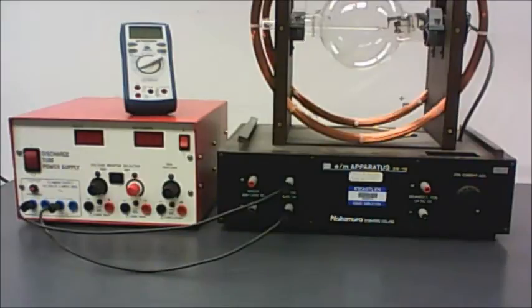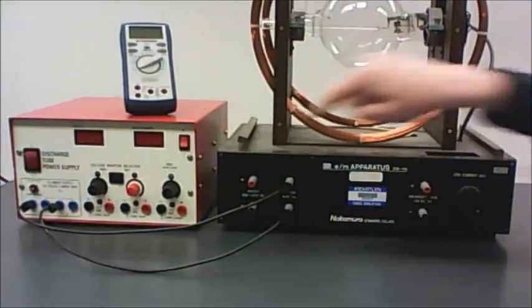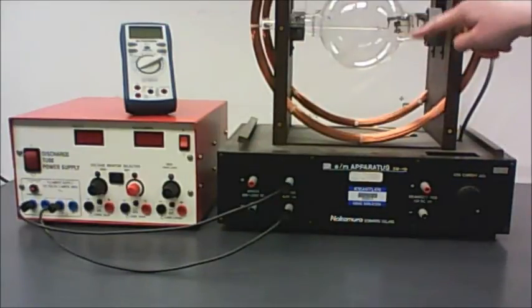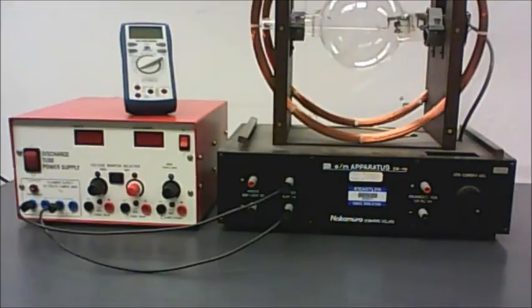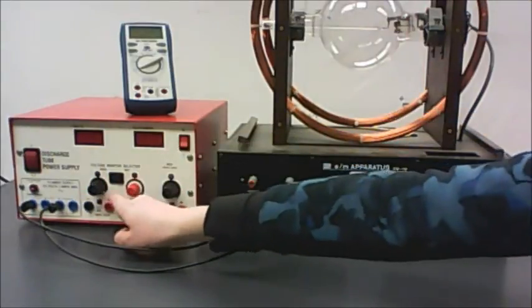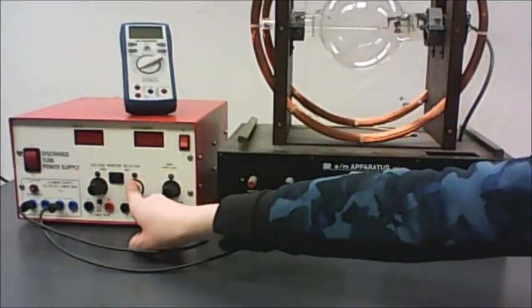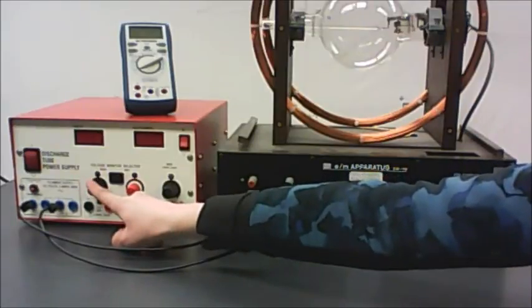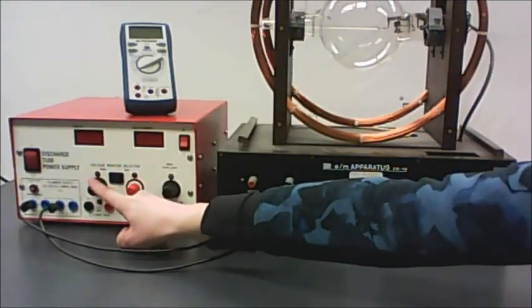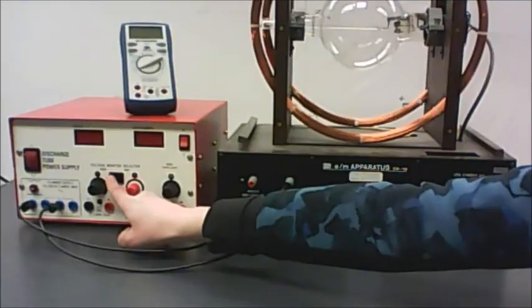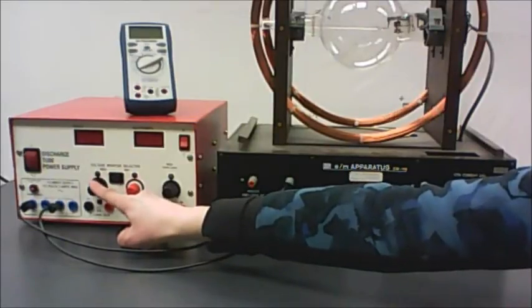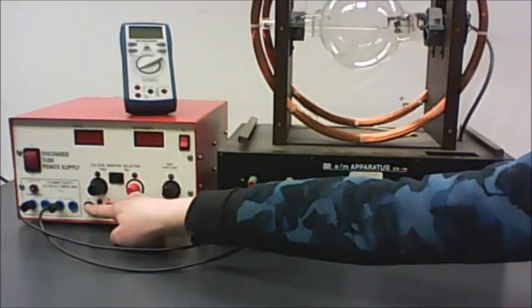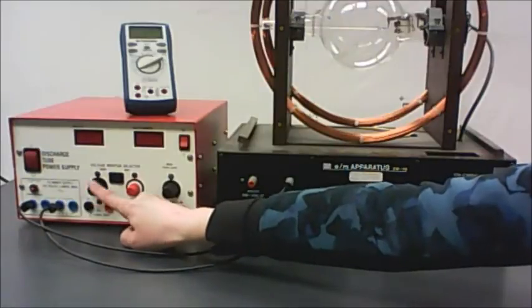The next thing we're going to hook up is the cables that give us the accelerating voltage. That turns our cloud of electrons into a beam of electrons. Those come from this terminal here. There's actually two voltage knobs. One of them says 500 volts, one of them says 80 volts. We want the 500 volt one, and you also want to make sure this switch in the middle is pointed towards the 500 volt knob. Then you plug in across the two terminals right underneath it.